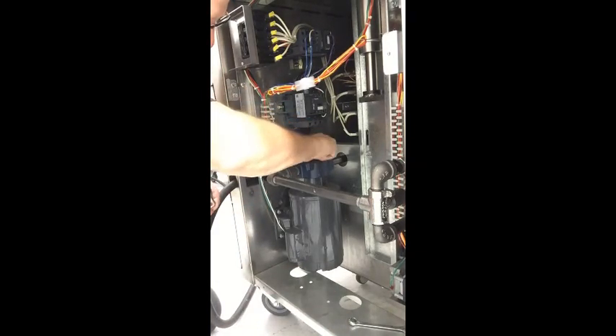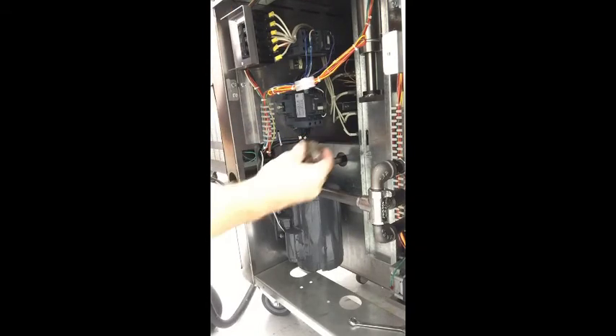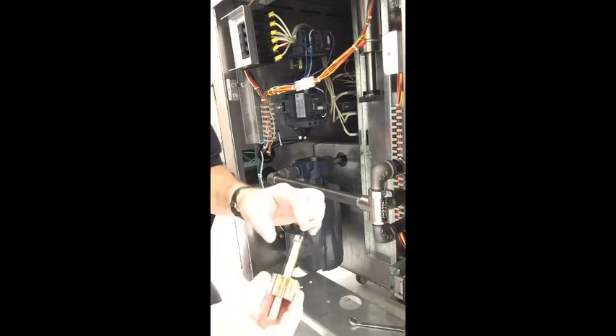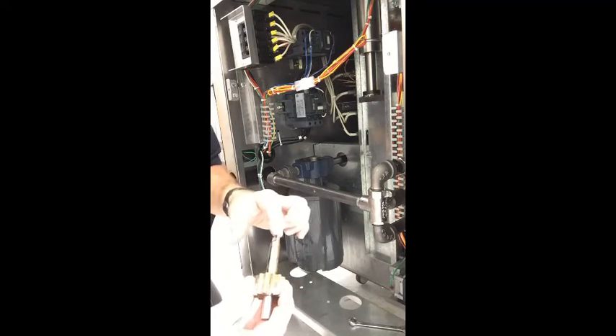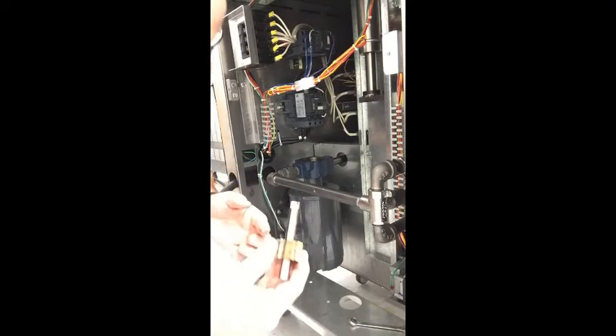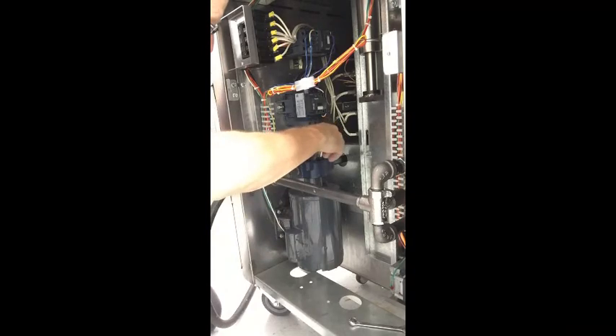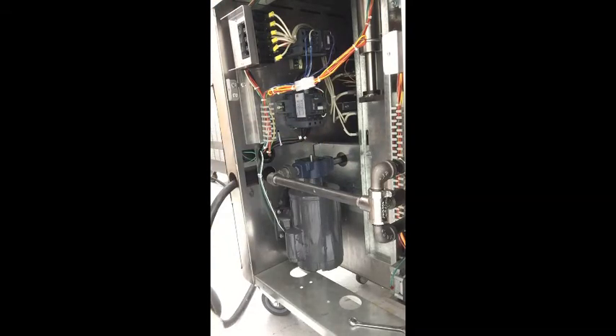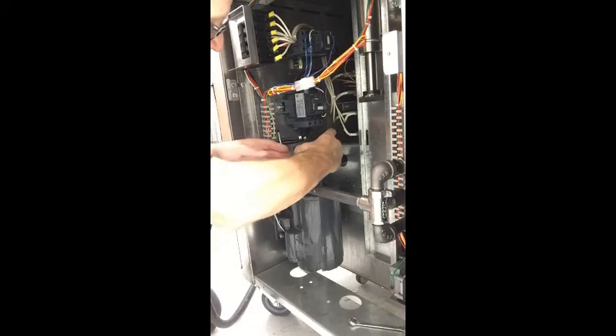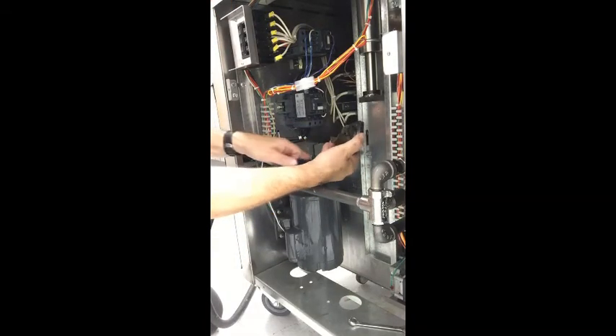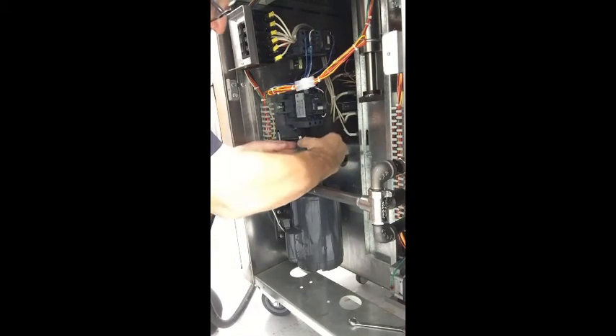You can pull this gear out and make sure that you've got it good and clean. This little piece right here is what goes down into the pump motor itself. This is the driver. So when you put it back in there, you'll have to make sure, turn it till it drops down into the motor, and it'll drop all the way down in nice and flush. Now once it does that, then we can go ahead and put our cover on. You'll see there's a gap on this side. This goes right there.